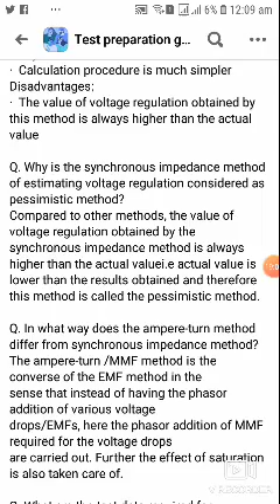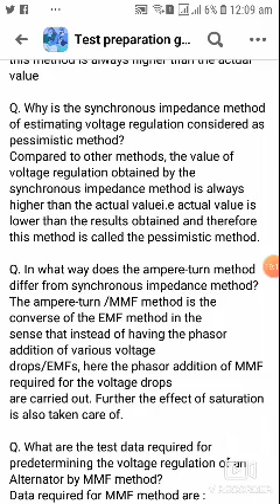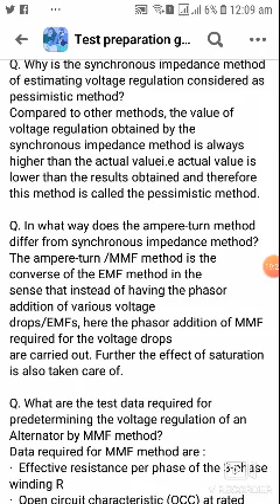Question number 35, why is the synchronous impedance method of estimating voltage regulation considered a pessimistic method? Compared to the other methods, the value of the voltage regulation obtained by the synchronous impedance method is always higher than the actual value. That means the actual value is lower than the result obtained, and therefore the method is called the pessimistic method.